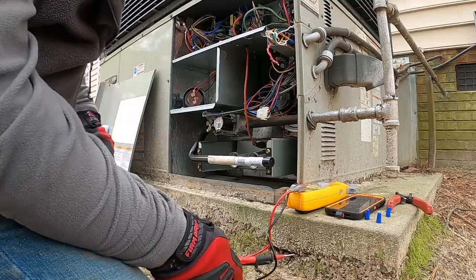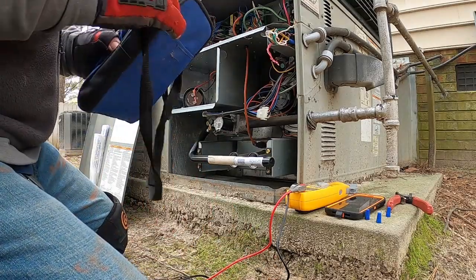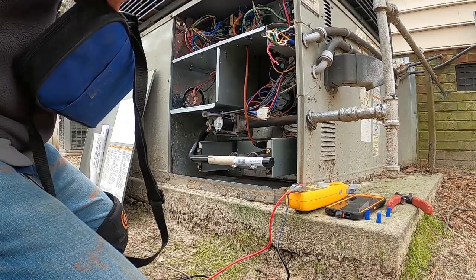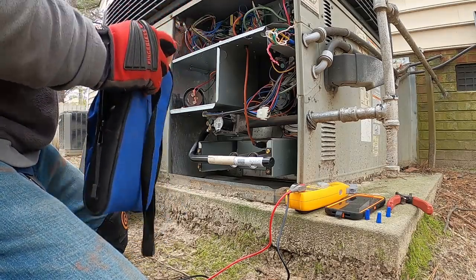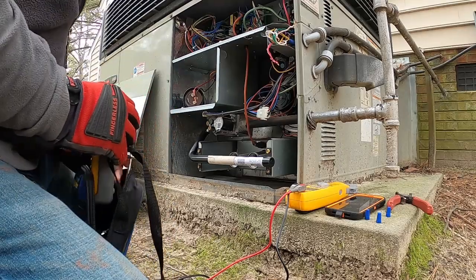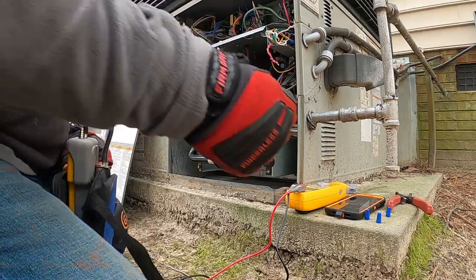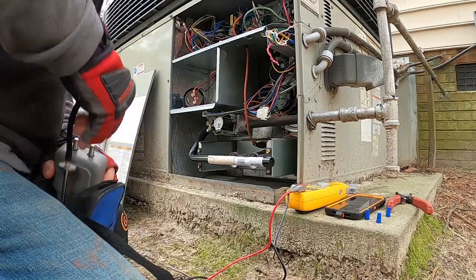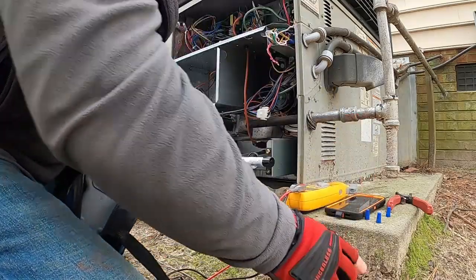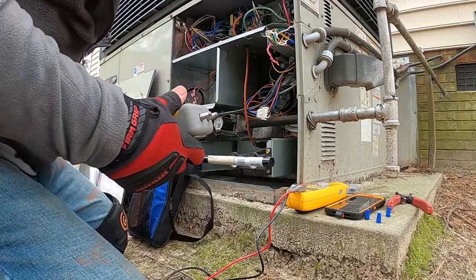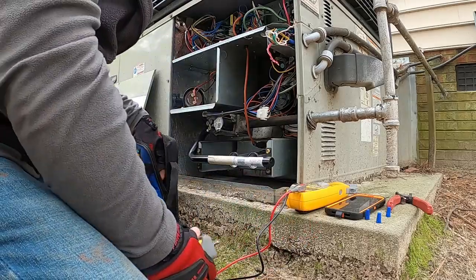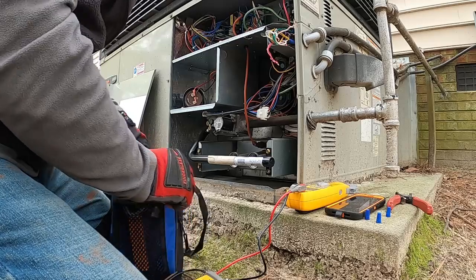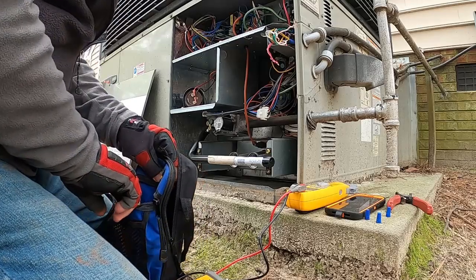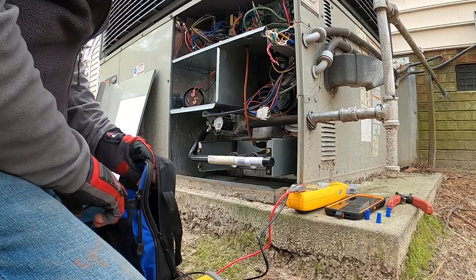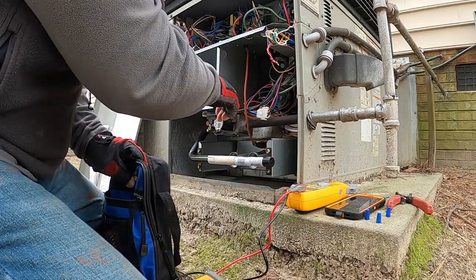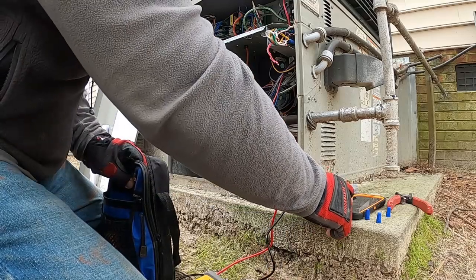So I want to check and see what kind of draft I'm getting from that draft motor and confirm basically whether my pressure switch is closing or not. There's a couple of ways to do it. I like to get a T fitting and run across the switch along with the motor and check everything in line, see what kind of draft is getting pulled.